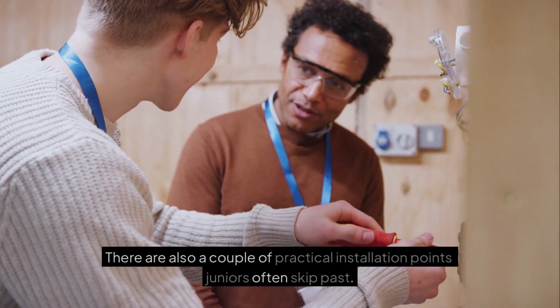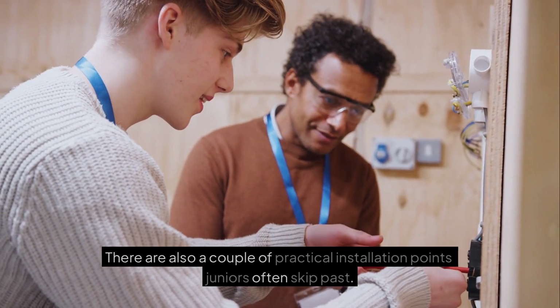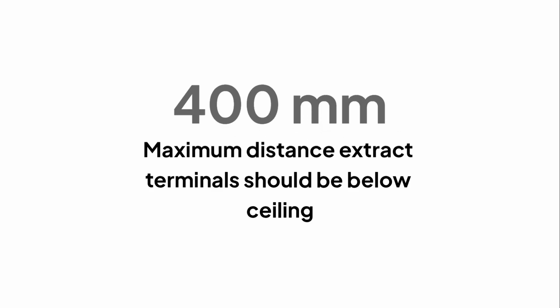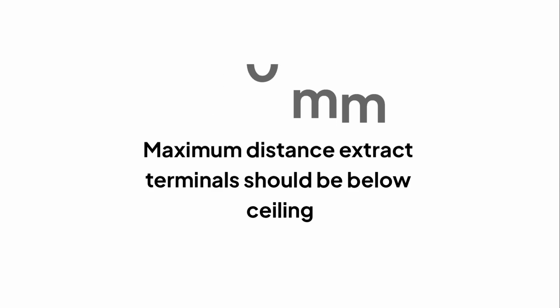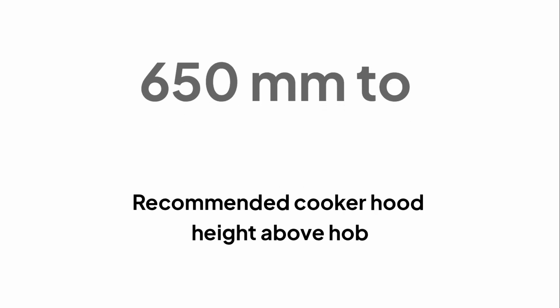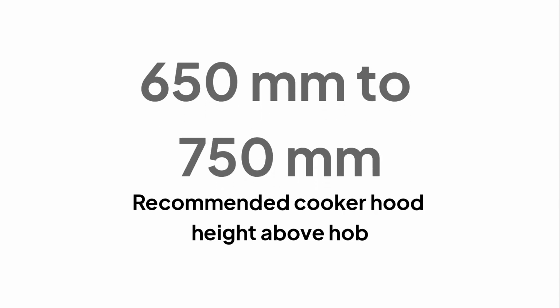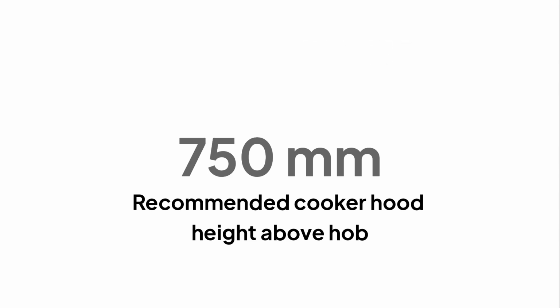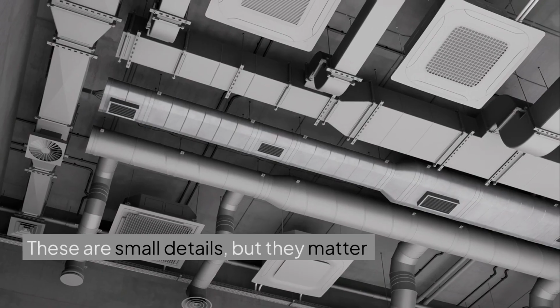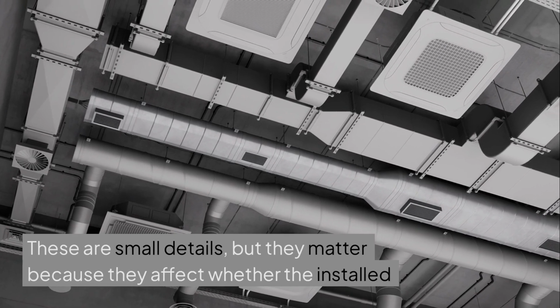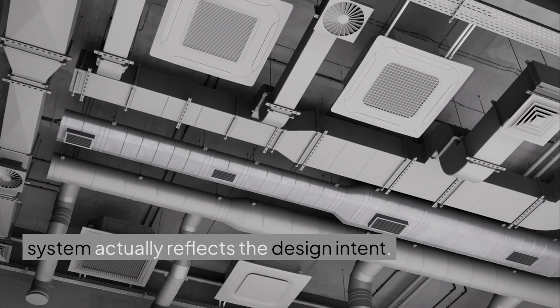There are also a couple of practical installation points juniors often skip past. Paragraph 1.16 says, extract terminals and fans, excluding cooker hoods, should be installed as high as practicable in the room and no more than 400 mm below the ceiling. Paragraph 1.17 says that where a cooker hood is used to extract to the outside, the height above the hob should follow the manufacturer's instructions, or, where unavailable, should be between 650 mm and 750 mm. These are small details, but they matter because they affect whether the installed system actually reflects the design intent.